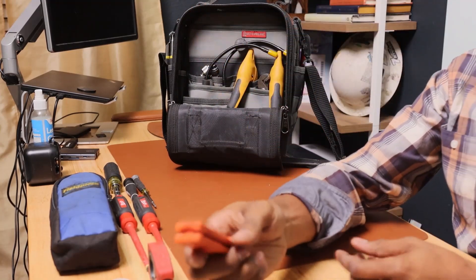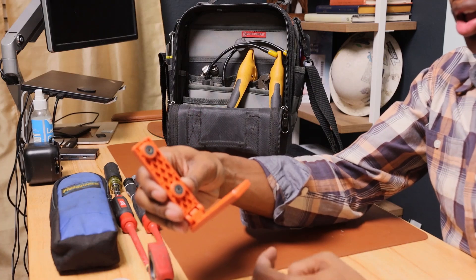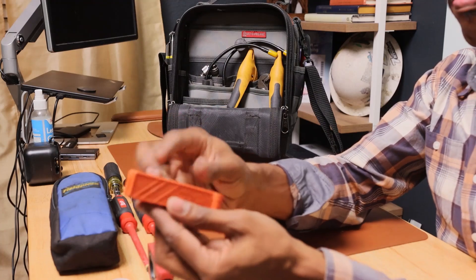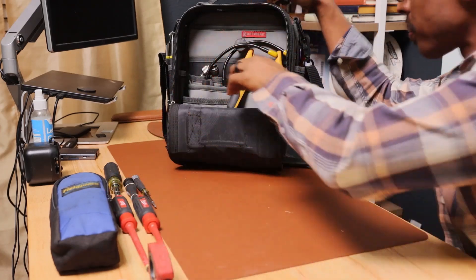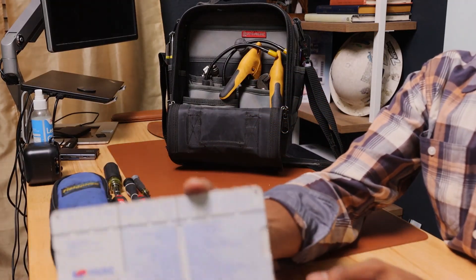I use this when troubleshooting a furnace — you need to have the circuit on but need the door closed. This tool, made by Supco, closes that door switch so you can work with the panel open.